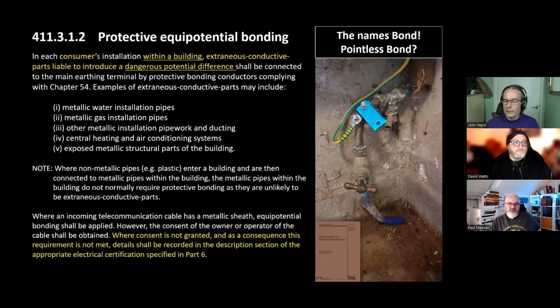It then has just rewritten a note where non-metallic pipes, plastic, enter the building and are then connected to metallic pipes within the building. The metallic pipes within the building do not normally require protective bonding. And then right at the end of the regulation, I haven't quoted all of it, there's a requirement for incoming telecoms cable, which I think we as an industry are terrible at, mainly because the telecoms industry is, in my personal experience, utterly terrible to deal with. Never mind surge protection of these sorts of things.